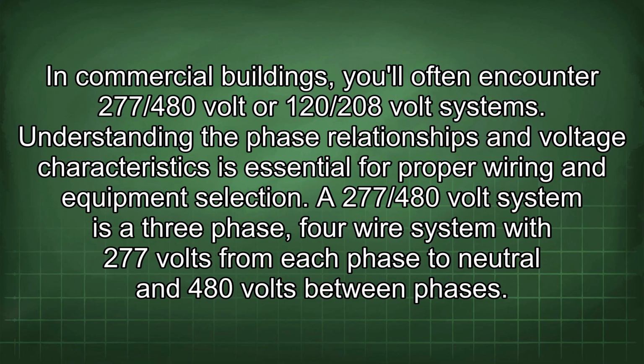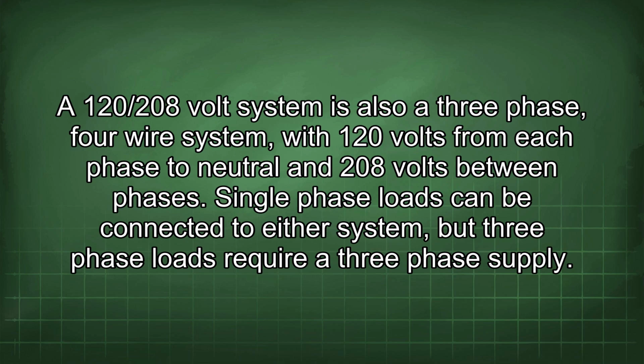In commercial buildings, you'll often encounter 277/480 volt or 120/208 volt systems. Understanding the phase relationships and voltage characteristics is essential for proper wiring and equipment selection. A 277/480 volt system is a 3-phase, 4-wire system with 277 volts from each phase to neutral and 480 volts between phases. A 120/208 volt system is also a 3-phase, 4-wire system with 120 volts from each phase to neutral and 208 volts between phases. Single-phase loads can be connected to either system, but three-phase loads require a three-phase supply.